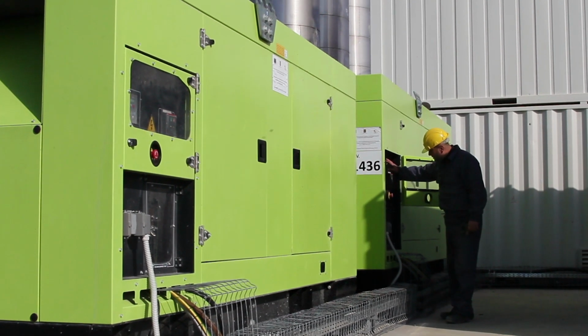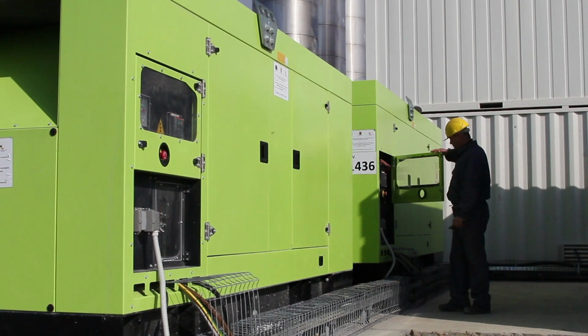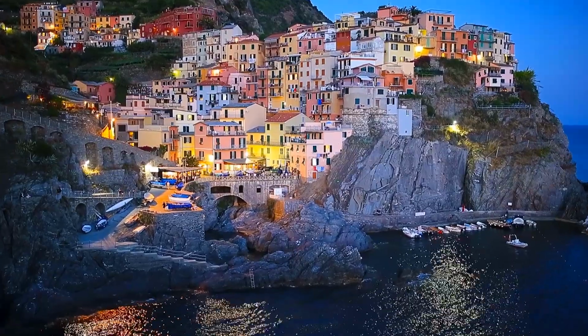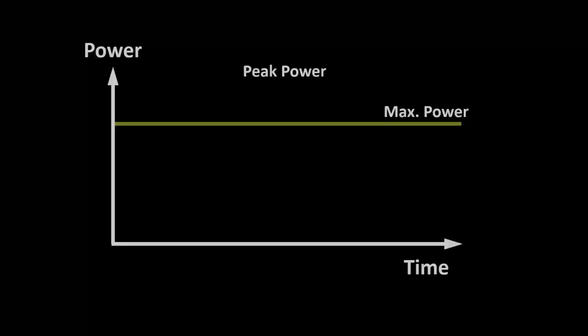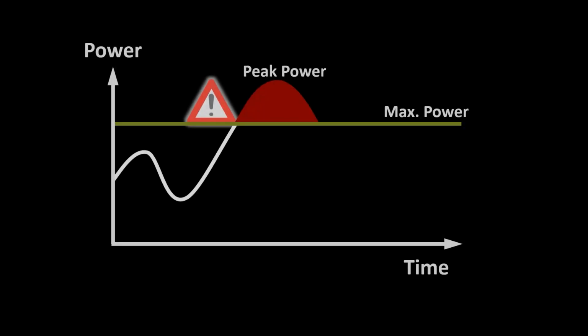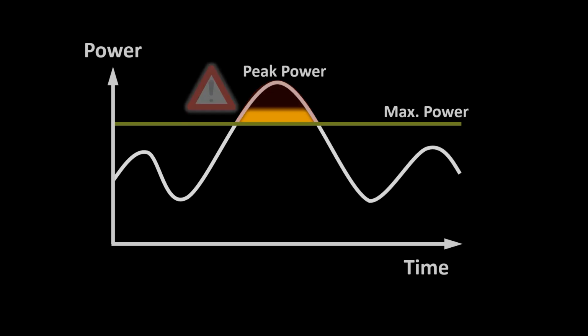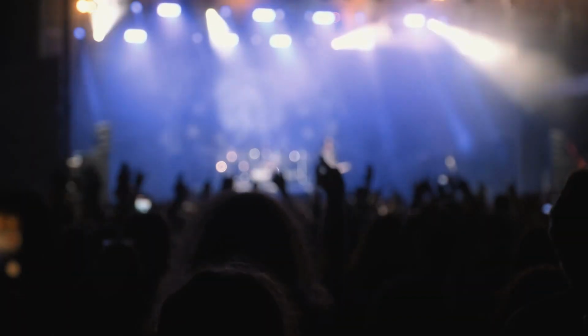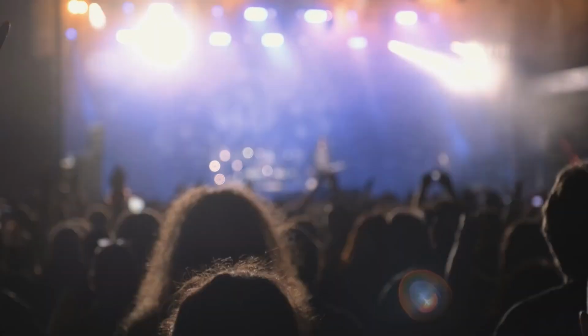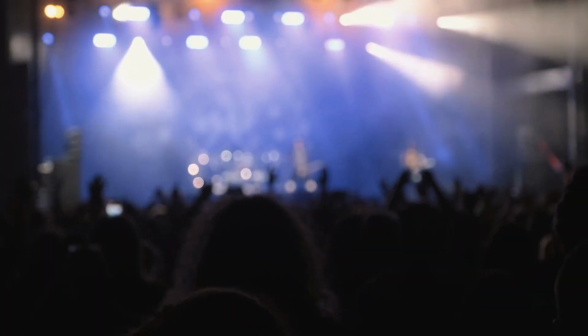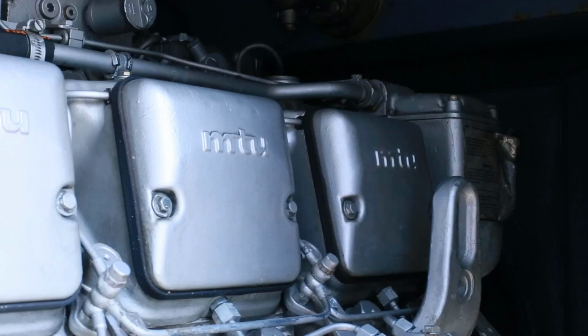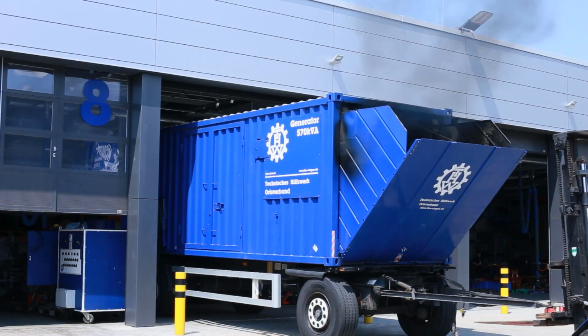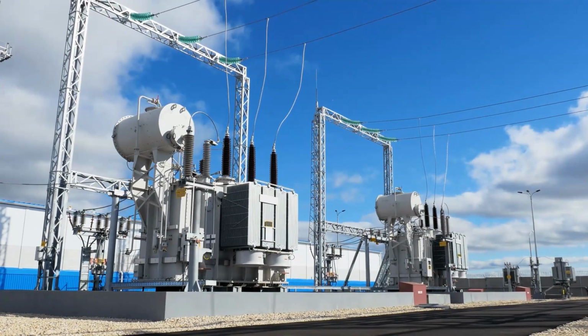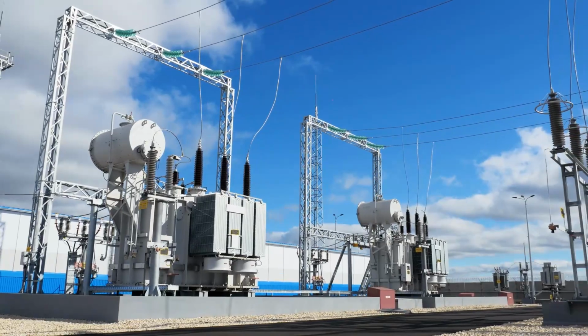Mobile generators can provide temporary power for various loads, like a small village or a district. Or mobile generators can work as peak shaving generators to ensure continuous power supply without any dips. This is often used on big festivals and large public events when the utility supply is not enough. Mobile diesel generators can also work as backup power, enabling technicians to service and maintain transformer stations.